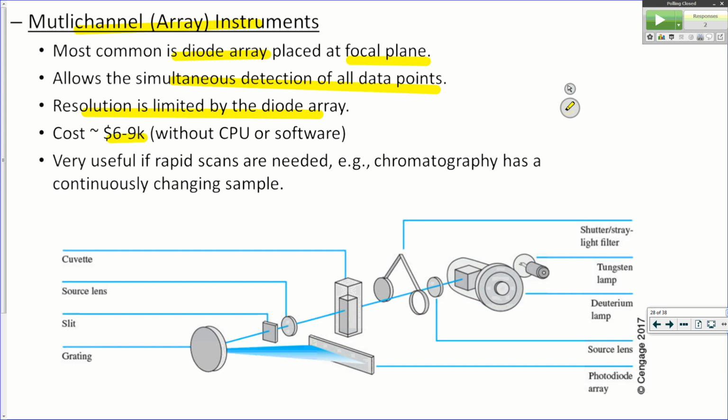And it could be that this is such an old instrument, when they first realized they could do that technology with it, they didn't even get that excited about it. I'm sure the newer stuff can do it. That one, you can't do a zero. So you can't get a true absorbance number without making a measurement and manually subtracting it.